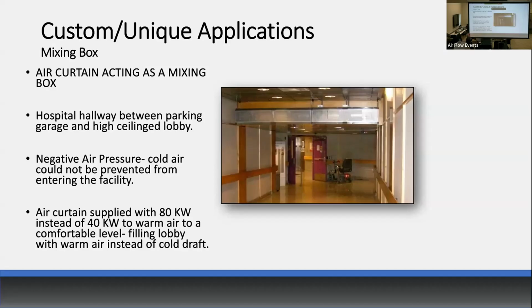And it's the mixing box. This is a hospital in Pittsburgh. They had a parking garage, a big long hallway leading into an atrium. Freezing cold air was coming in through the winter. They could not heat it up. So they wanted to use an air curtain as a mixing box. This is a 12, I believe it's a 12-foot wide unit. This would normally have 40 kW, which would give you about a 30-degree temperature rise. They said, put as much heat in there as you can physically fit. We were able to double it. So we put 80 kW in there, giving a 60-degree temperature rise.